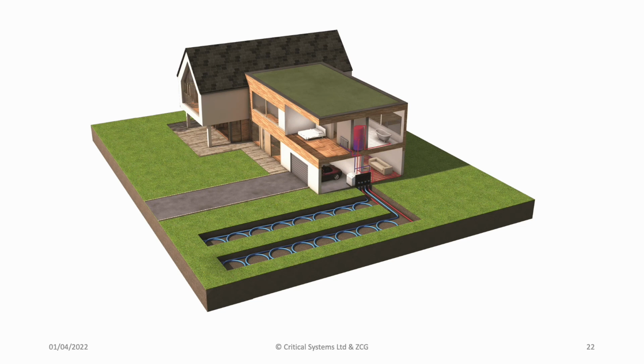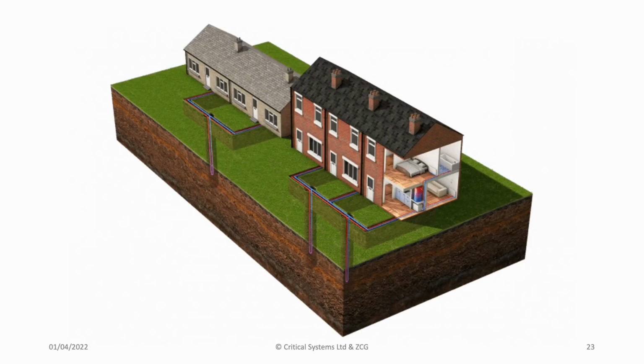So this diagram just illustrates a horizontal array, and some rules of thumb suggest the area could be close to or similar to the plan area of the property. An alternative for ground source is a borehole solution, and this could be applied to a single property, or a heat network could be provided such that a number of properties are engineered to share the same ground source.